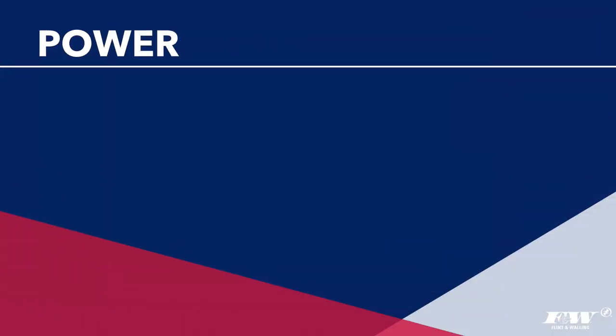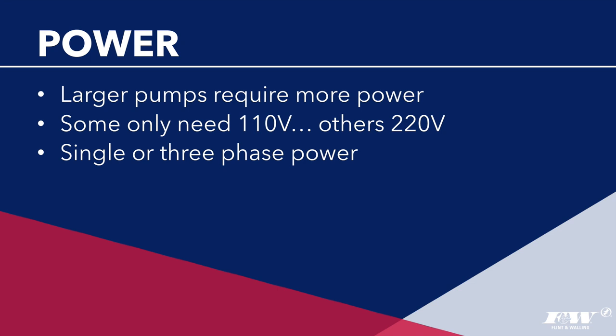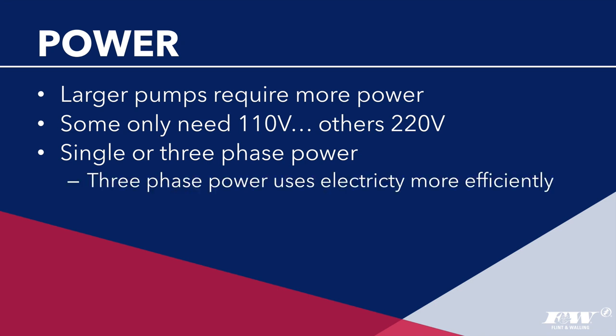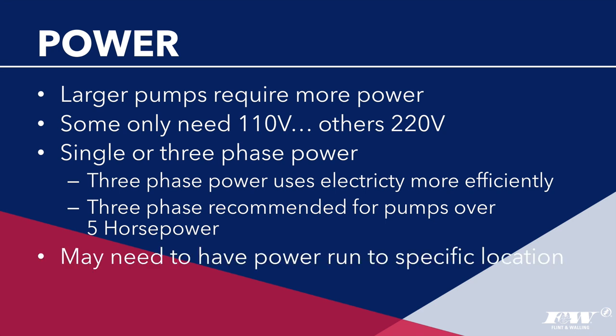All pumps require power, and the bigger the pump, the more power it needs. A small booster pump may only need a regular 110-volt outlet, while larger pumps require a 220-volt or larger connection. Pumps are also designed for either single-phase or three-phase power. Three-phase power isn't available at all locations, but where it is, the pump uses electricity more efficiently with smaller wires. Three-phase power is recommended for pumps over five horsepower. Before ordering, you'll need to know the voltage available and whether the power is single-phase or three-phase, and arrange with an electrician if needed.